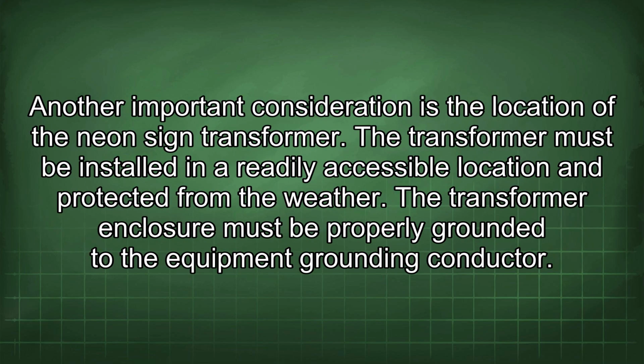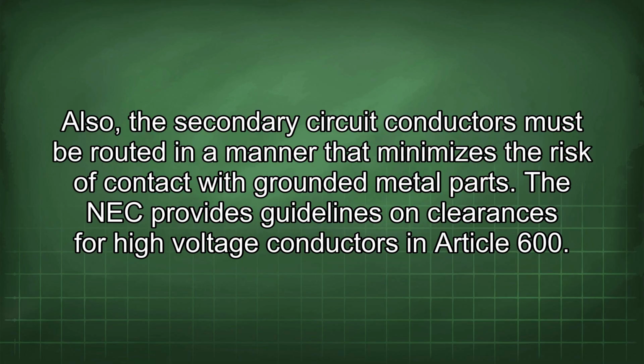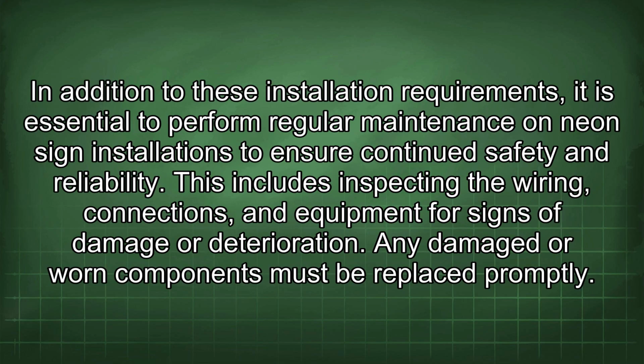Another important consideration is the location of the neon sign transformer. The transformer must be installed in a readily accessible location and protected from the weather. The transformer enclosure must be properly grounded to the equipment grounding conductor. Also, the secondary circuit conductors must be routed in a manner that minimizes the risk of contact with grounded metal parts. The NEC provides guidelines on clearances for high-voltage conductors in Article 600. In addition to these installation requirements, it is essential to perform regular maintenance on neon sign installations to ensure continued safety and reliability. This includes inspecting the wiring, connections, and equipment for signs of damage or deterioration.